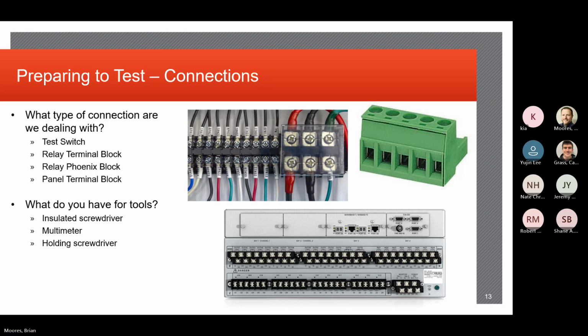So you might need a little mini insulated screwdriver for these green Phoenix blocks, because those are actually pretty small. You see those more on maybe communications with their smaller gauge, 22, 24 gauge wire. A lot of the time on the relay connections, you're number 10, number 12, number 14 gauge. Most of the time in some of these bigger power type terminals, you could get up to 8 gauge, but you're not really going to see much more than that on the back of a relay.